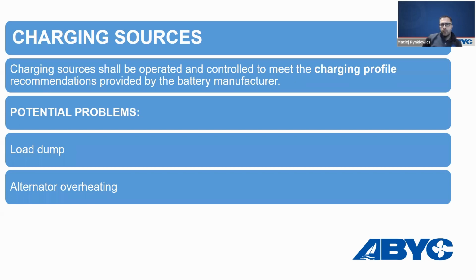And that's not a use problem, that's more of an installation problem. So that's something that needs to be figured out in the installation phase. And there are multiple ways to address that problem. It's pretty straightforward. You can use DC to DC converters, you can use battery isolators, you can use a second, for example, lead-acid battery, and connect that with the isolator to your lithium-ion bank. So there are a few ways to address the load dump.